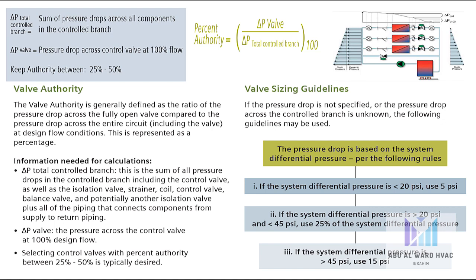We also have the valve authority, which is generally defined as the ratio of the pressure drop across the fully open valve compared to the pressure drop across the entire circuit including the valve. Percent authority equals ΔP across the valve divided by ΔP across the total controlled branch.